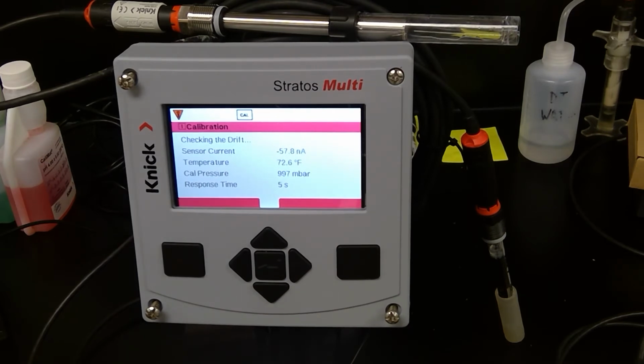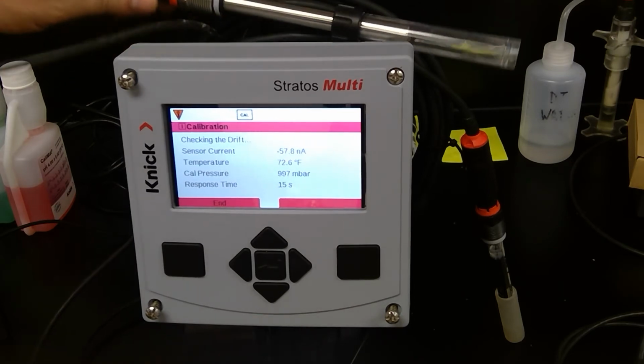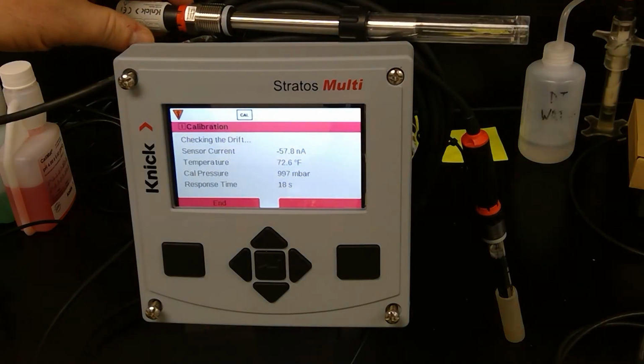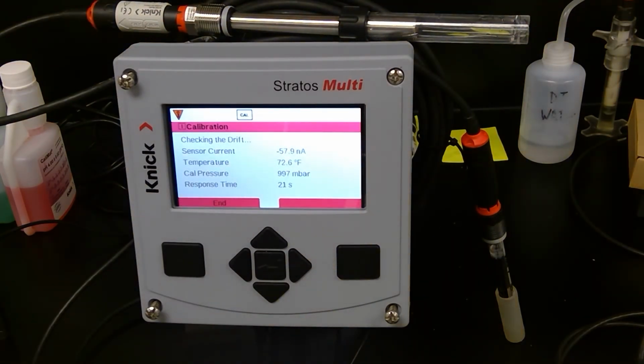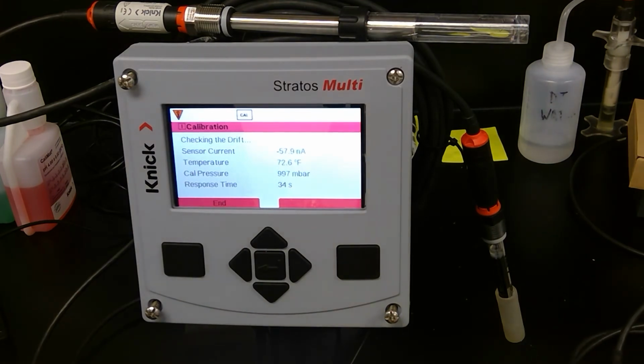Now, a couple of important things while this goes through the calibration, which should take exactly 60 seconds. Once you're finished with the calibration, that calibration information is saved in the head of the electrode. So now I'll be able to carry that out to the field and do a hot swap with the sensor that's already out there. Keeping in mind, ideally, you want to connect it to a Portavo if it's going to be disconnected or if it's going to take you more than 5 minutes to get out to the field. So what you'll be doing is ensuring the polarization is good.